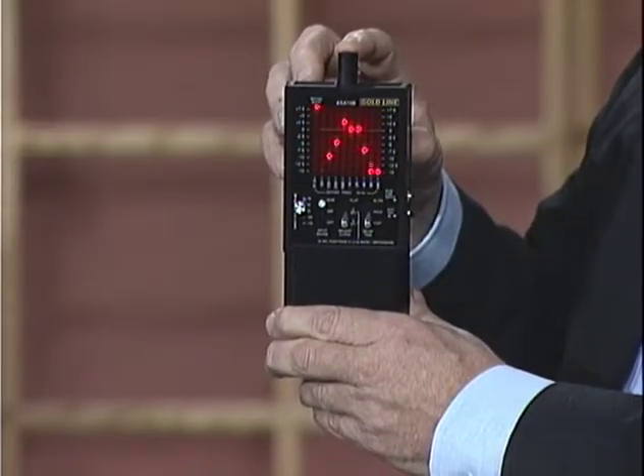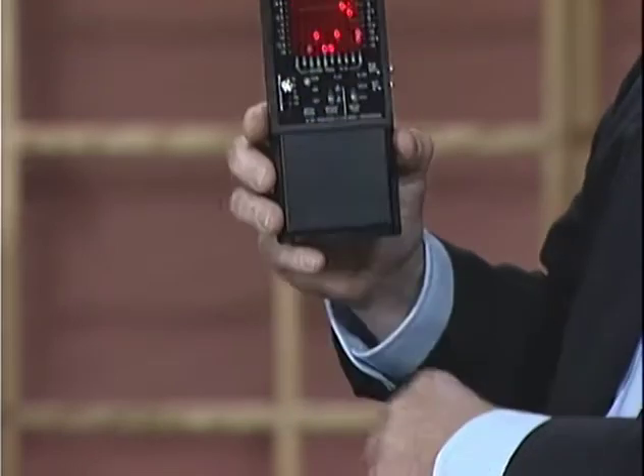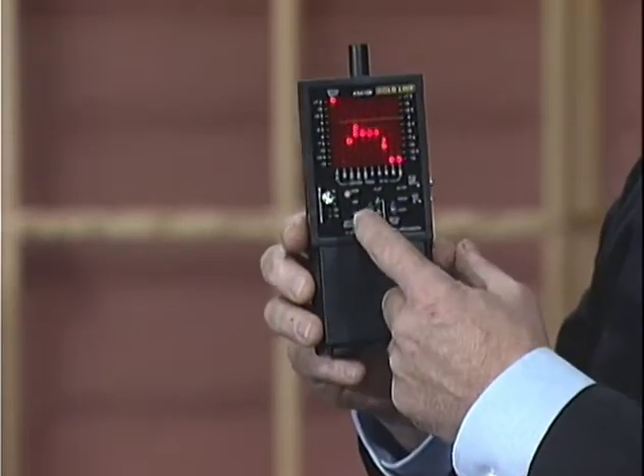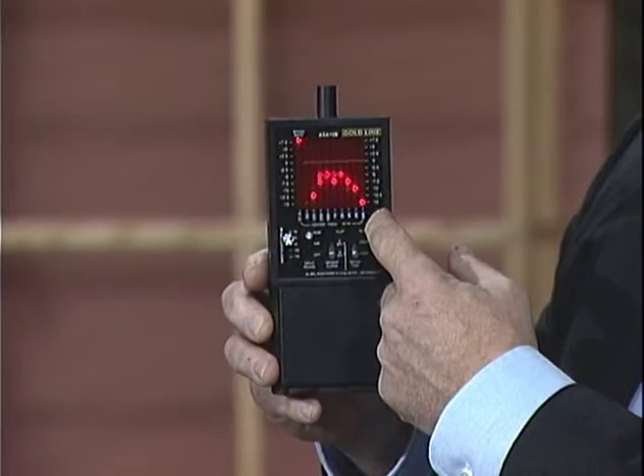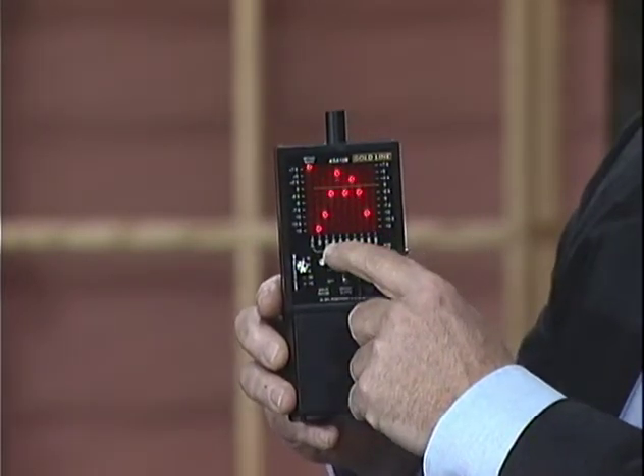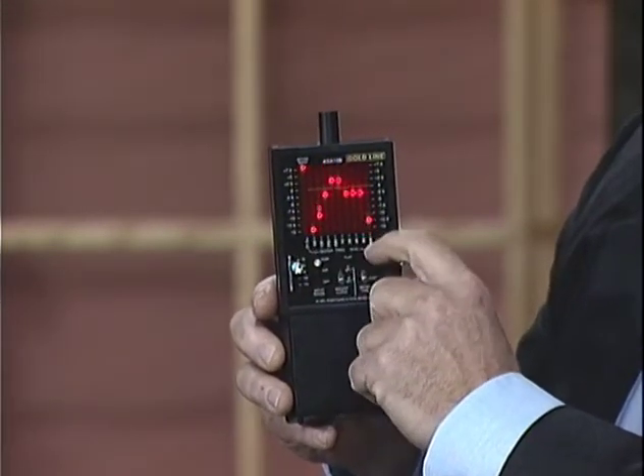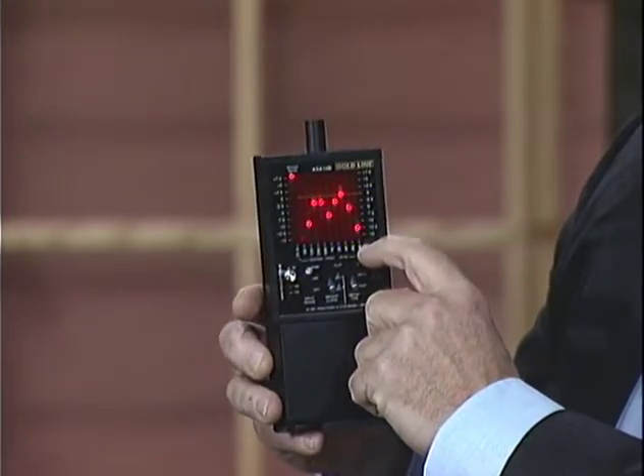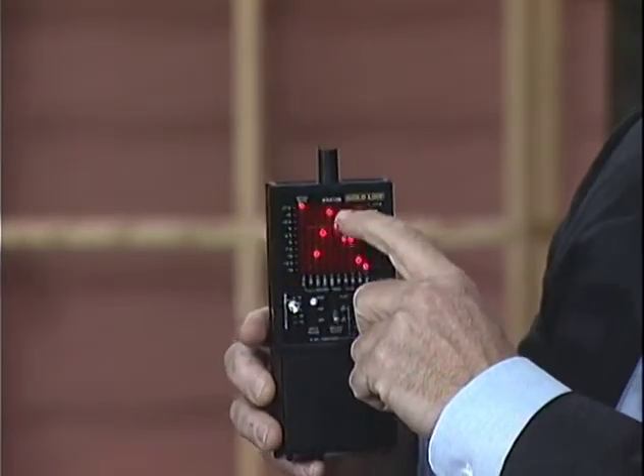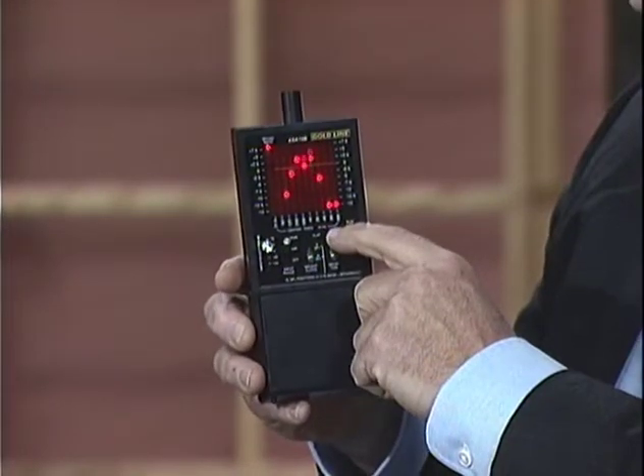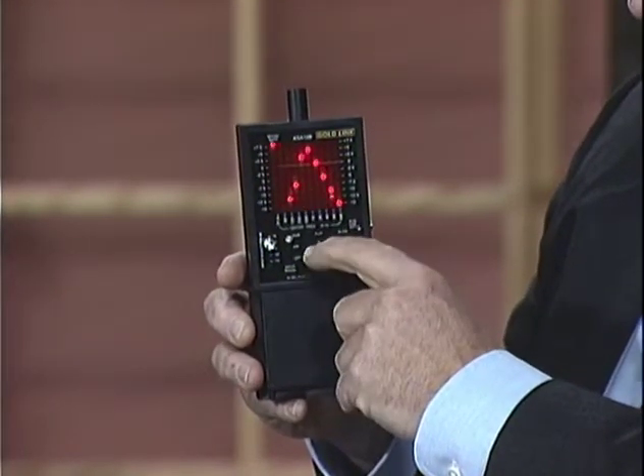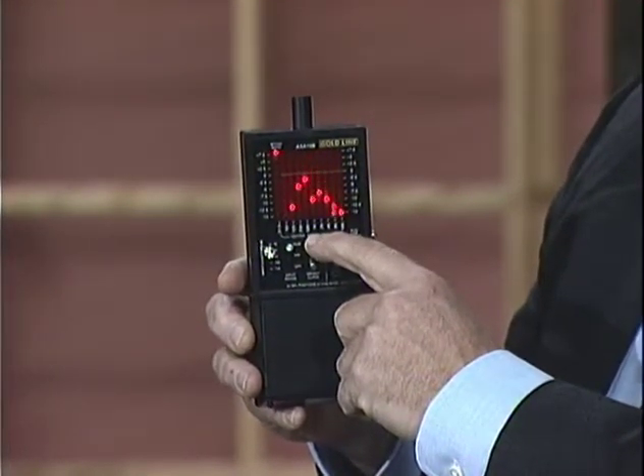You can set this meter up so that when you turn it on, you'll see a series of red lights. These red lights are the sound pressure level in the space as measured by this microphone on top of the meter. Small and compact, it's fairly effective in giving you a frequency spectrum as well as the dB level in the space. The spectrum goes from 16 or 31 hertz up to 16,000. The dB levels are pretty much from 30 dB up to 123. You can do linear scale or A scale.